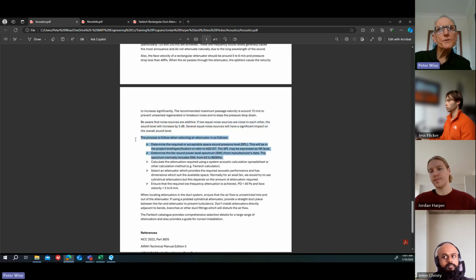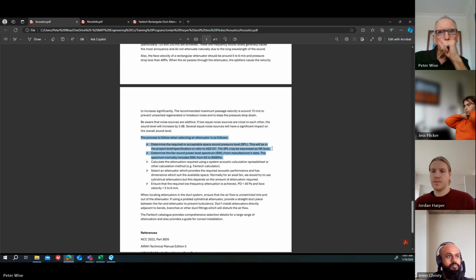So a simple process when selecting an attenuator is, firstly, we need to determine the required or acceptable space sound pressure level. We talked about this last week. This should be in the project specification or the project brief. If it's not there, there might be an acoustic report for the project. That should specify what's required for the space. If it's not there, we can refer to AS 2107, which has got recommended sound levels. And remember that the SPL or sound pressure level may be expressed as an NR level, which is noise rating level.